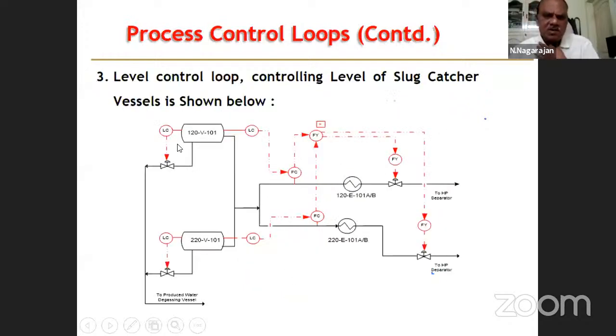A level control loop controlling the level of slug catcher vessels is shown below. I think we have seen two vessels are there, which are operating on the level controls on the water stream, and the hydrocarbon level controller on the two vessels is fed to the flow control here, and they are regulating the flow to the HP separator. The same thing, it is divided into two streams, and the level control from the separator vessel is linked with the flow control here.